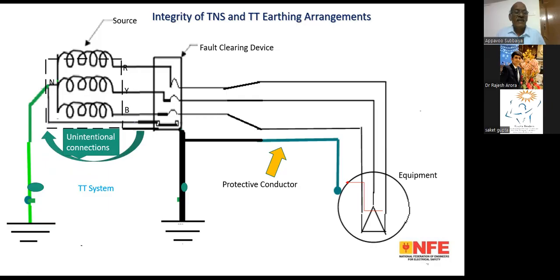And one more thing: what we do in a TT system is we are inadvertently connecting many things, because, for example, we connect the cable armor and we connect the bus duct. These are connected to the frame, but in the installation, the frame's earth electrode will be interconnected with the source neutral earth electrode. Thereby, you will have an unintentional connection that can result in an inefficient TN-S system or an inefficient TT system. So you can't have a design value for either the TT system or the TN-S system unless you provide an installation where this is not occurring. That's why I say the TT systems that we claim in our installations actually become an ineffective TN-S system. Here, the cable armor will have to carry the fault current, and the general mass of earth will also have to carry it.